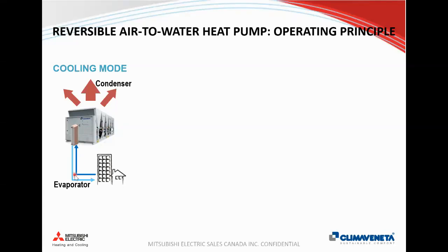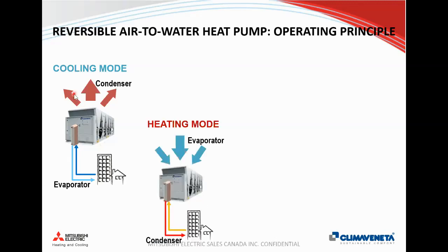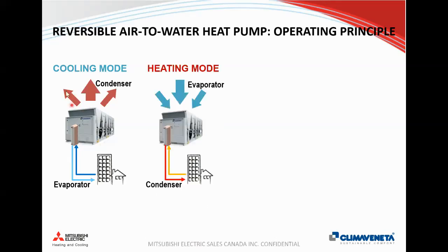So to provide chilled water to cool our building in fan coils or air handling units, in order to provide that chilled water, we need to reject heat from the building to the outside. We're doing that through an integrated condenser coil in the machine that's acting as a condenser in that refrigeration circuit. A reversible heat pump is essentially that same refrigerant circuit. They're designed a little bit differently, but they have a four-way reversing valve inside the machine to switch the direction of the refrigerant flow.